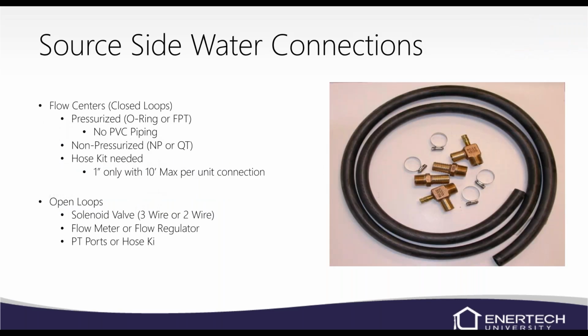So basically, on our units, we have the source side water connections, and it's going to depend on the type of flow center what different types of connections. Most of our units now, you guys are probably aware, we use the double O-ring fitting. There's some water-to-waters out there that don't, and a couple other units that don't, but the majority of them will use the 1-inch double O-ring fitting.